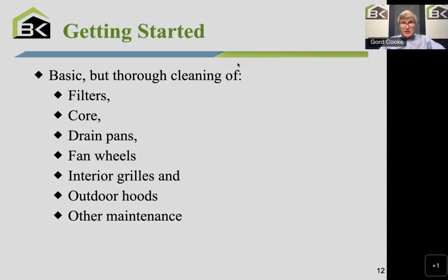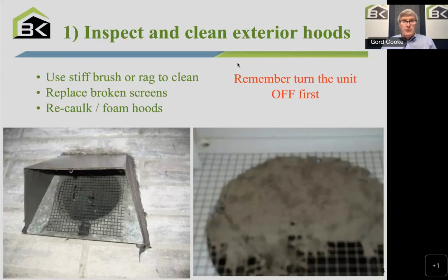And these are the elements on our list. And we're talking about maybe half an hour of work in most cases. So not too bad. So let's start with, we've turned the unit off. Remember, turn the unit off, and you're going outside and understanding that the fresh air intake, typically near the ground, about 18 inches above the ground, gets full of grass clippings and pollens and dusts and so on, depending on the season, maybe leaves in the fall.